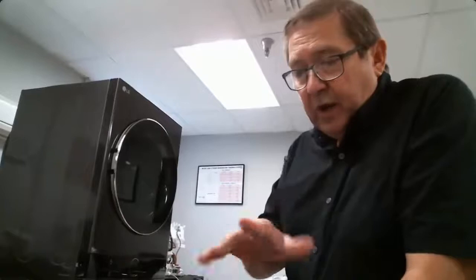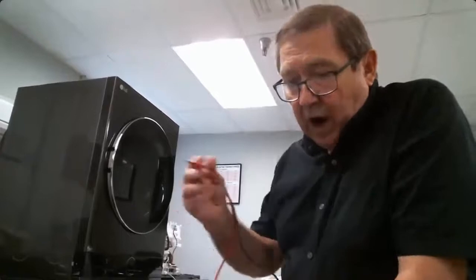This is DC voltage, and the problem with these meters is they don't like seeing pulsating DC voltage. So if you want to get a voltage reading, set it for AC voltage. These meters will pick up alternating current, similar to our pulsating current, and we'll be able to get a reading. Guys, this is pretty high voltage—you're probably going to get readings above 200 on these things, so be careful if you're checking for voltage down to the stator.